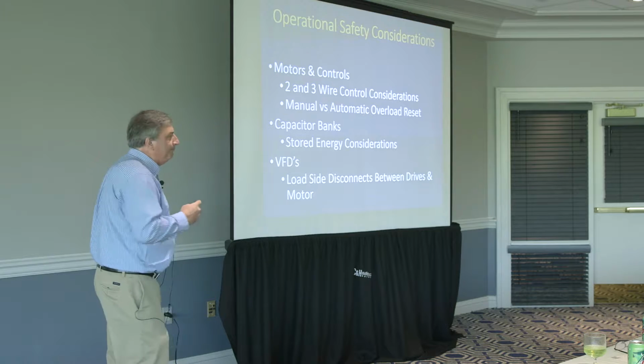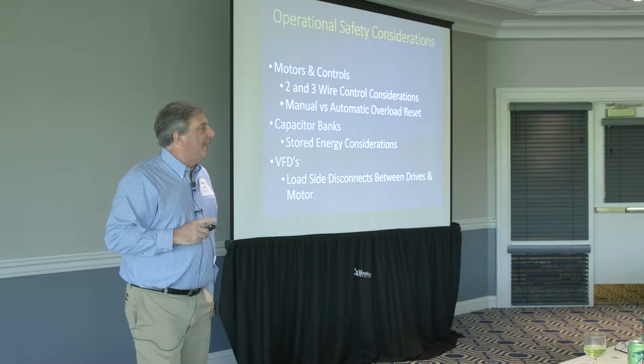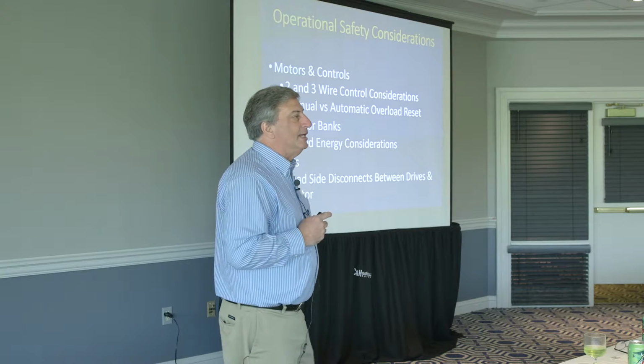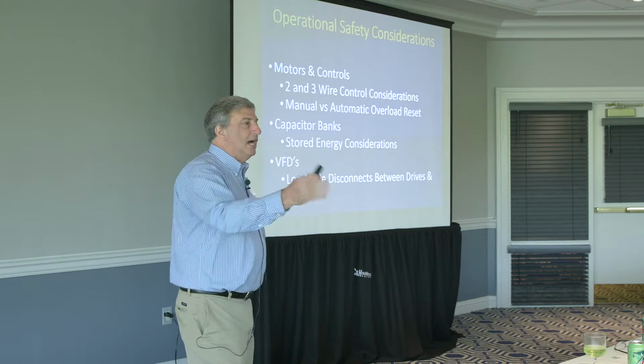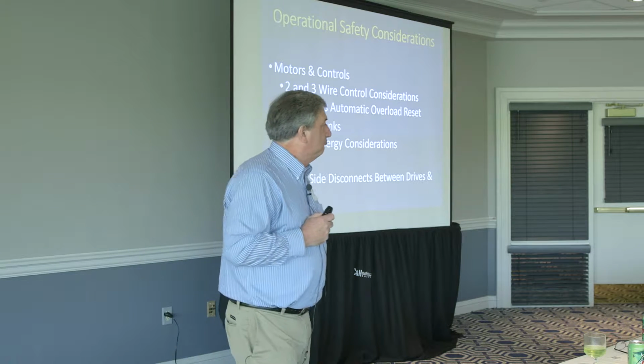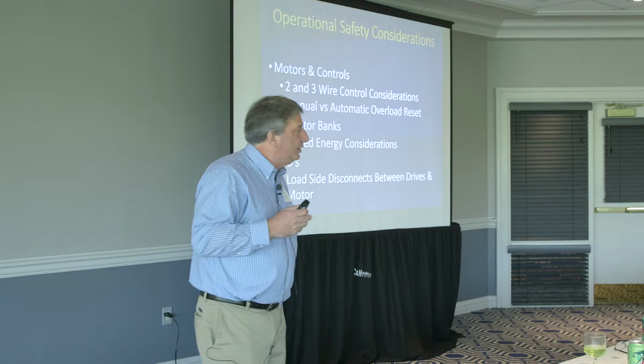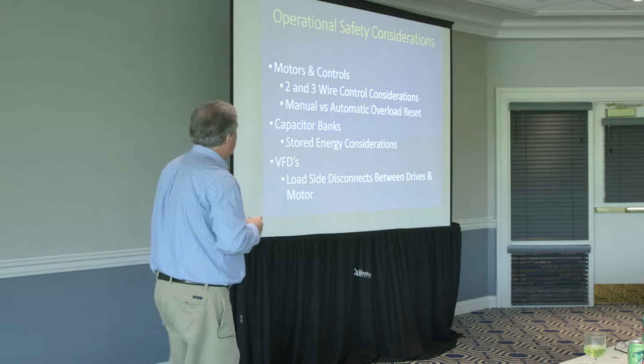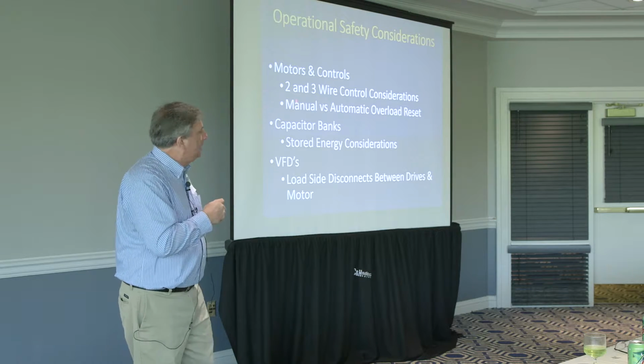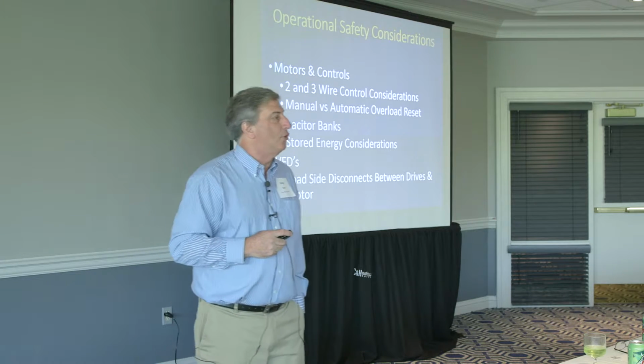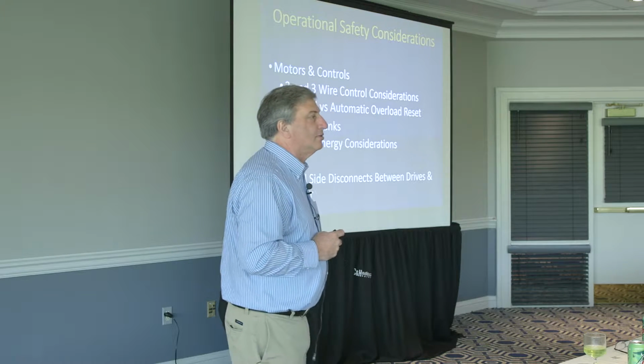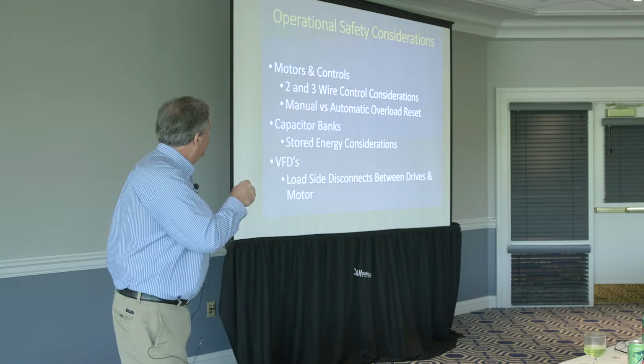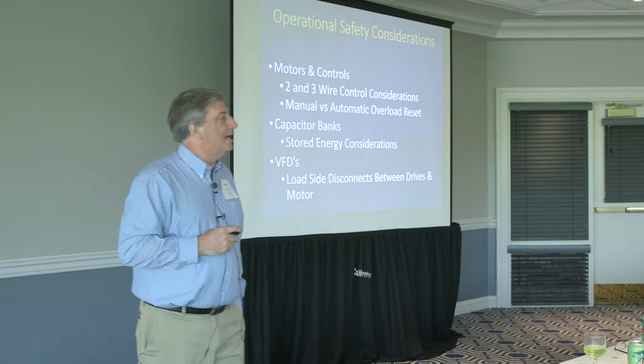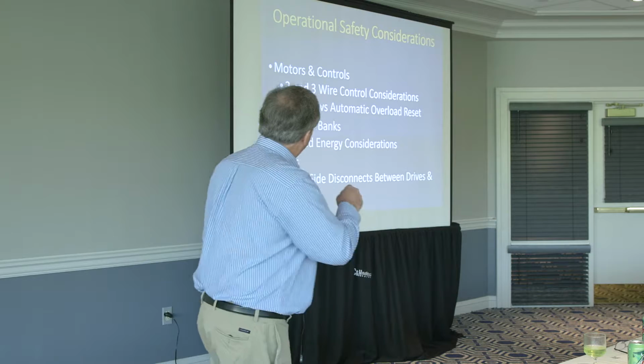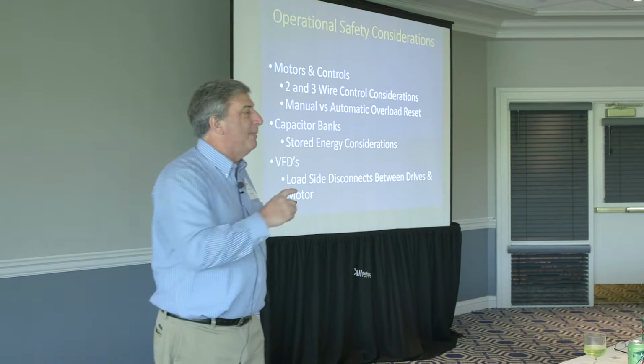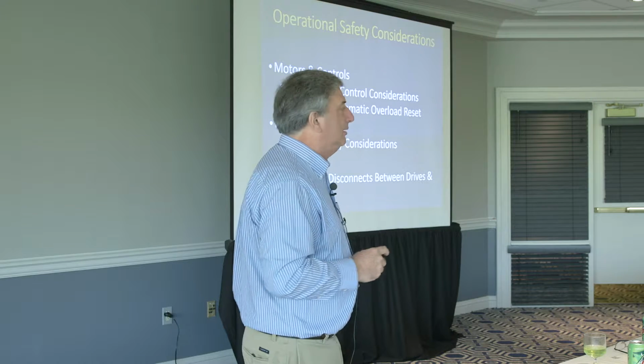hurt? And I said, okay, if I really start looking at what I get involved in, I surmise right now that many of the really young folks coming into your facilities that may have some experience with equipment and maintenance practices don't understand as well as maybe they should the difference between 2- and 3-wire control of motor starters and motors, and the differences in safety and automatic starting capability that 2- and 3-wire control considerations and manual and automatic overload reset imply.